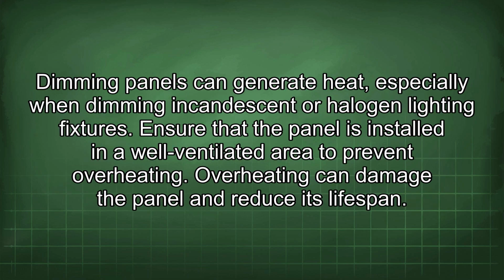Dimming panels can generate heat, especially when dimming incandescent or halogen lighting fixtures. Ensure that the panel is installed in a well-ventilated area to prevent overheating. Overheating can damage the panel and reduce its lifespan.